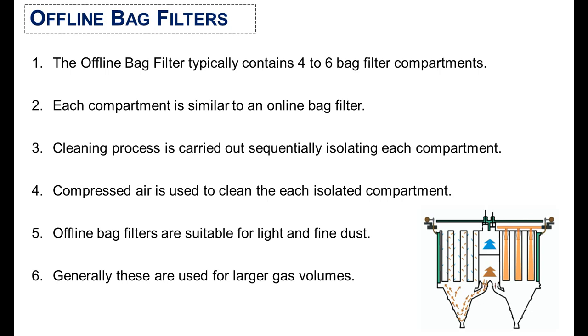Offline bag filters contain four to six bag filter compartments, and each compartment is similar to an online bag filter. The cleaning process is carried out by isolating each compartment, and compressed air is used for cleaning. Offline bag filters are suitable for light and fine dust and have the capability to handle large gas volumes.